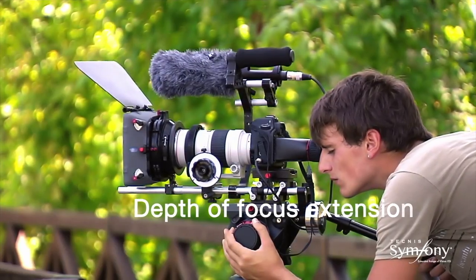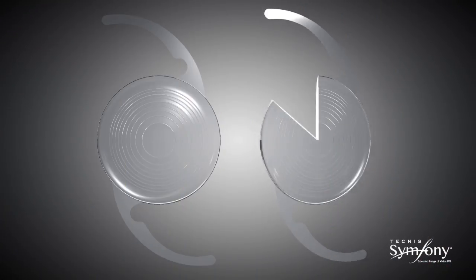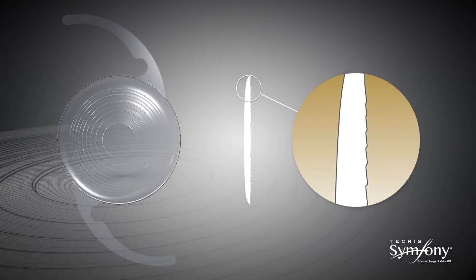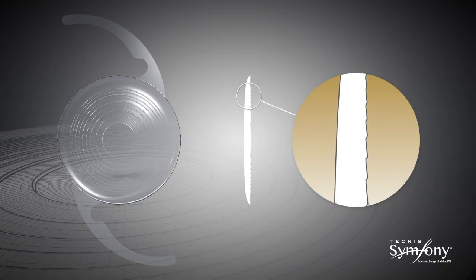The new Symphony lens uses diffractive optics to extend the depth of focus into a focal range by designing the steps on the backside of the IOL in just the right way so the light focuses over a large range of distance.